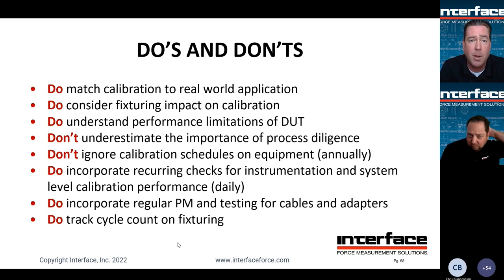So, calibration escape. Incorporate regular PM and testing for cables and adapters. Sometimes it's the simple things that need to be followed up on, right? Is there an issue with a cable? Is there an issue with an adapter? Are the sense leads not correctly connected through the adapter? Have the adapter pins been fatigued to a point where they're not engaging properly and you're getting intermittent contact? The simple things always need to be considered in these types of critical applications such as calibration. And then cycle count on fixturing, as mentioned a couple times now, they do have a fatigue life, they do wear out, and it does have significant impact on calibration.